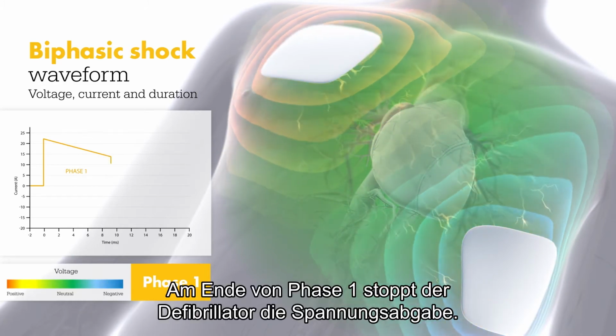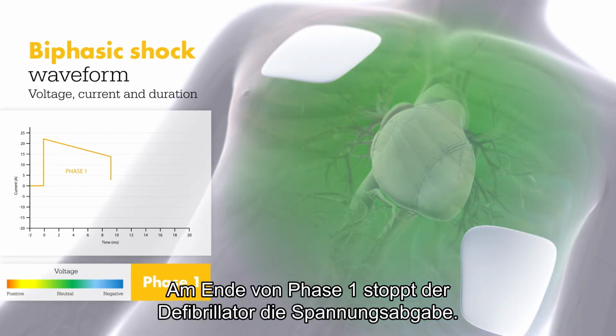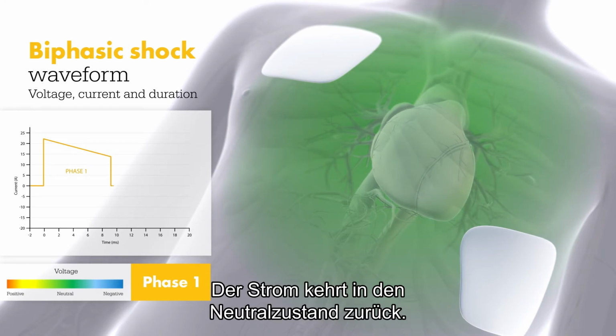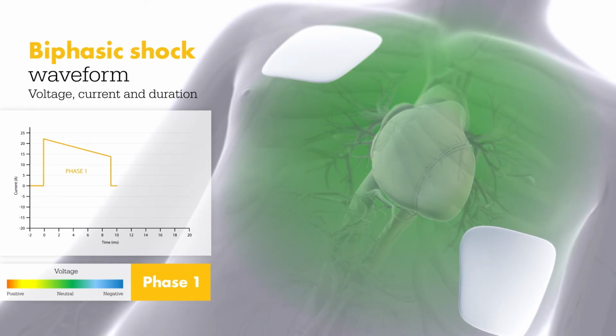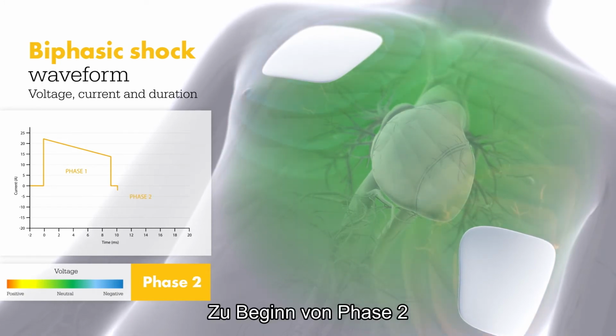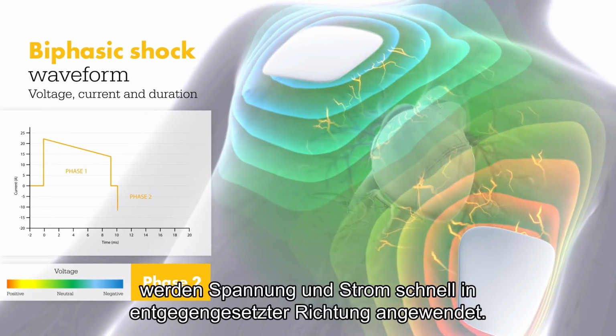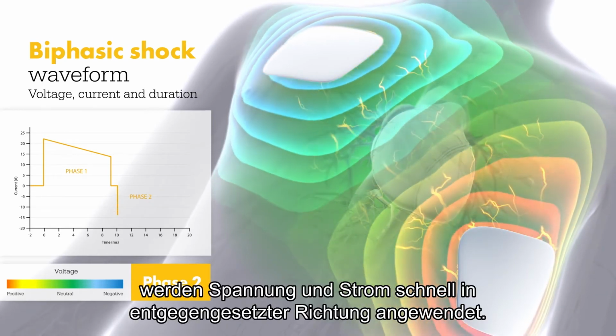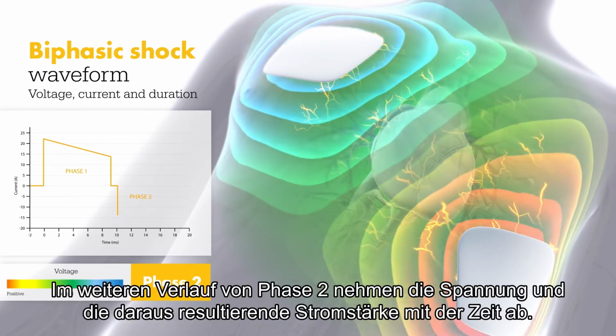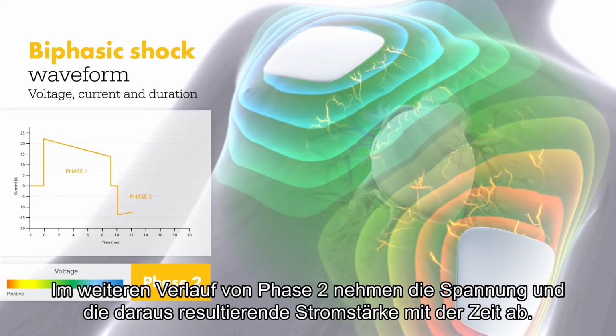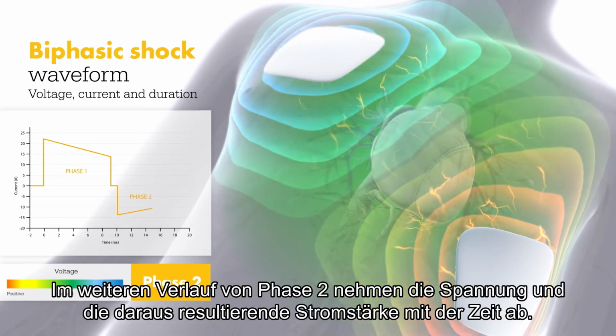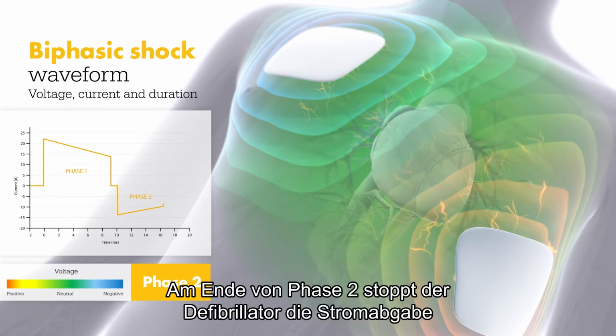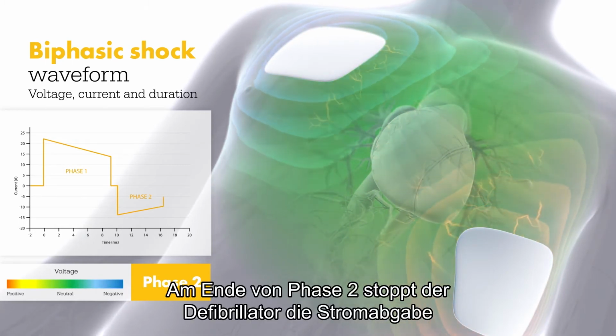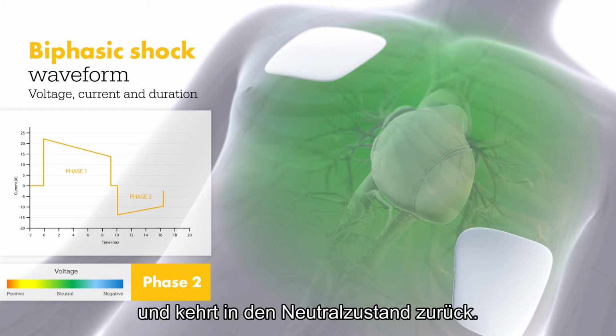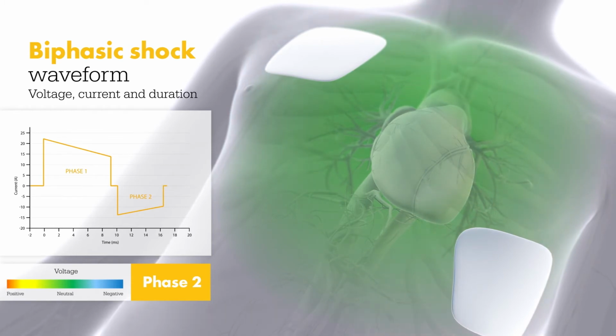At the end of phase 1, the defibrillator stops applying voltage, which shuts off the current to return to a neutral state. At the start of phase 2, voltage and current are quickly applied in the opposite direction. As phase 2 continues, the voltage and the resulting current decreases over time. At the end of phase 2, the defibrillator shuts off the current, causing a return to neutral. The shock is now complete.